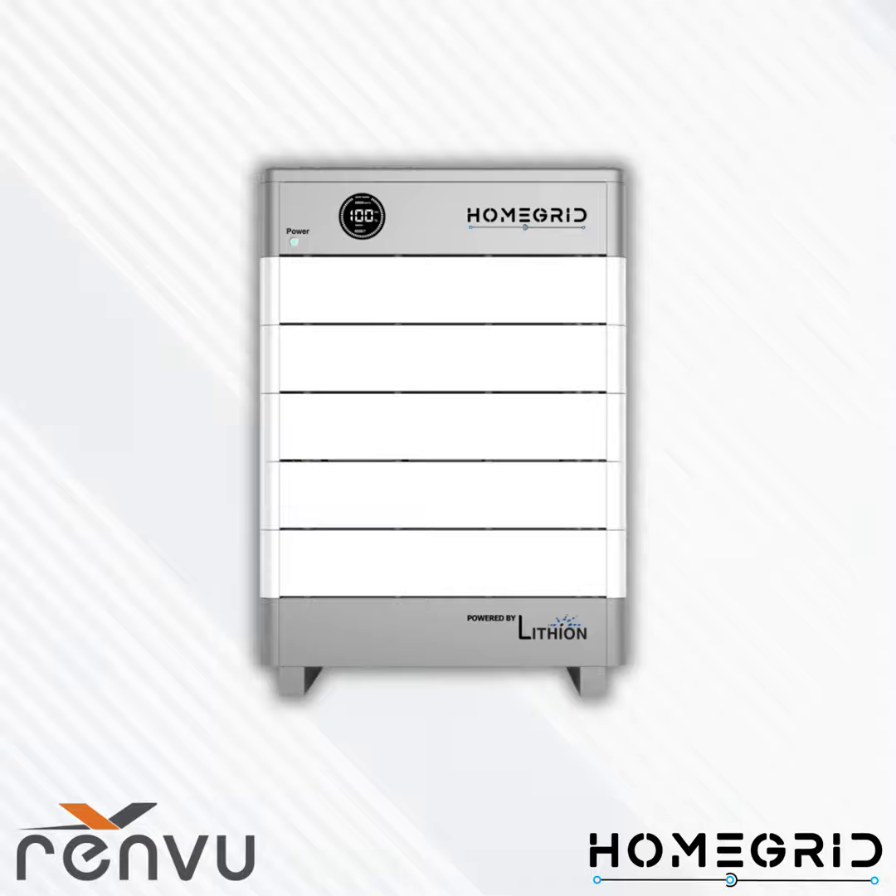For state of charge parameters: do not put batteries into storage at less than 60% state of charge. Batteries in storage need to be charged back to 60% every six months. If the battery reaches 0% for 12 hours, it needs to be charged to at least 5% to resume normal operation. To get the app set up, call our tech support line at 855-753-3505 or download from the Google Play or App Store.